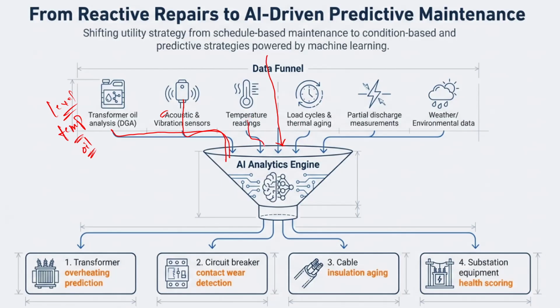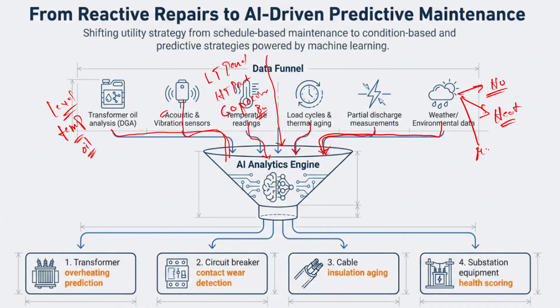The temperature reading is not only for the transformer — we can get temperature readings for the LT panels, HT panels, capacitor banks, and so on, as well as for the sensors themselves. We also have to get details of thermal aging, the load cycle, partial discharge measurements, and weather data, which could be humidity level, heat, temperature of the environment, moisture, and so on.